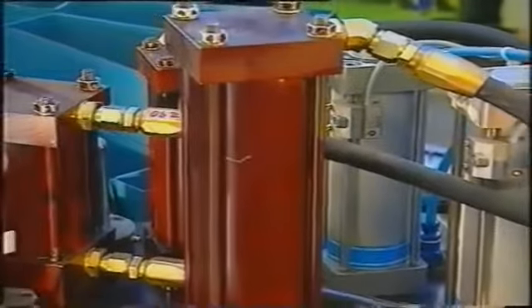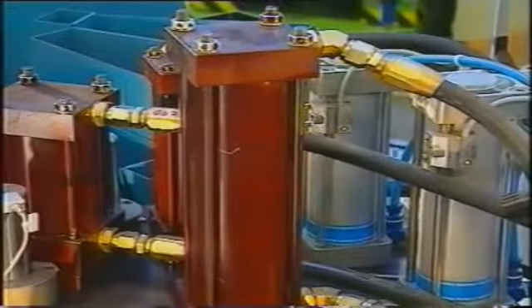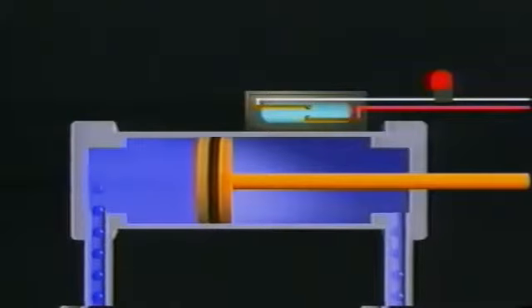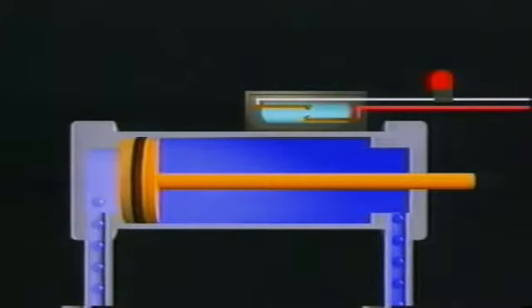This proximity switch has a contact that is magnetically actuated. Its uses include position interrogation on pneumatic and hydraulic cylinders. A permanent magnet on the piston attracts the movable contact tongue. The circuit is closed. Here too, a permanent magnet on the cylinder triggers a signal. Its magnetic field influences the field of an inductive sensor. The electronic circuit detects this change and opens or closes the circuit.